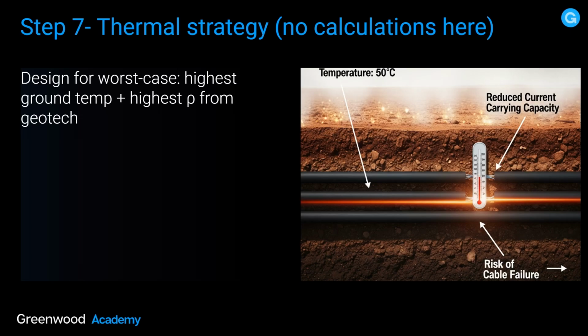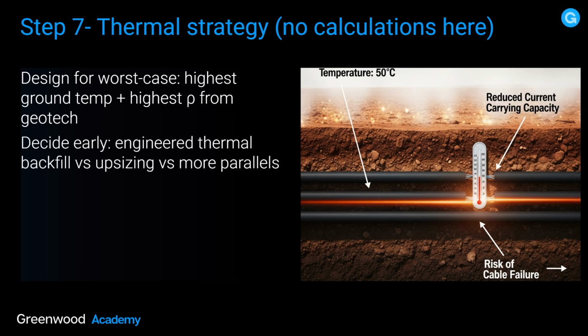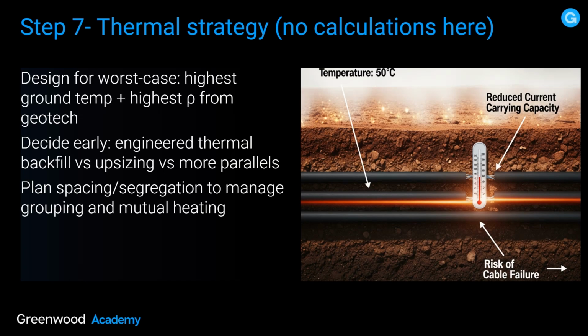Step 7, thermal strategy. No calculations here. So you design for worst case, highest ground temperature and highest thermal resistivity from the geotech. Decide early, engineered thermal backfill versus upsizing versus more parallel cables. Plan spacing, segregation to manage grouping and mutual heating.